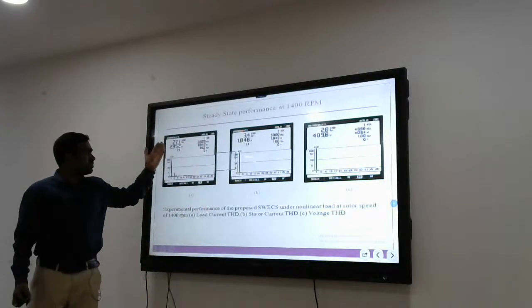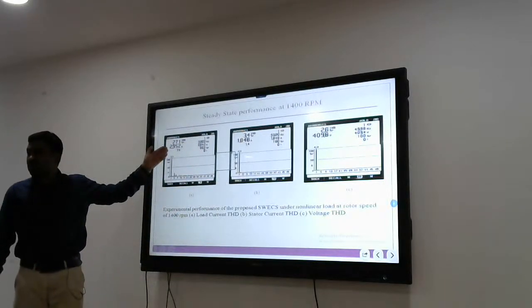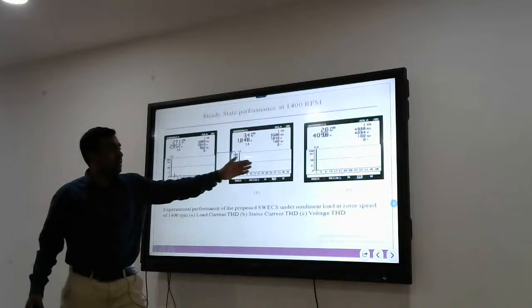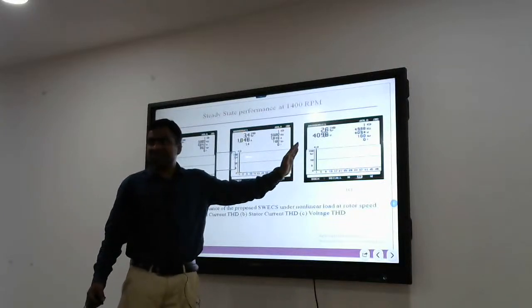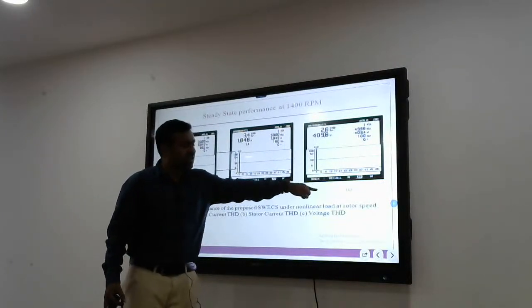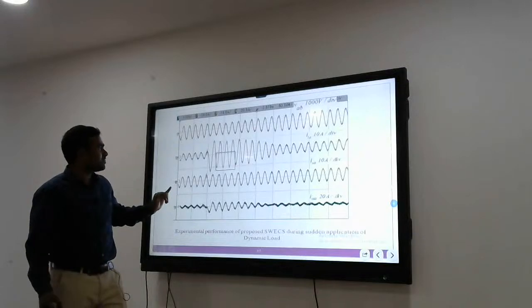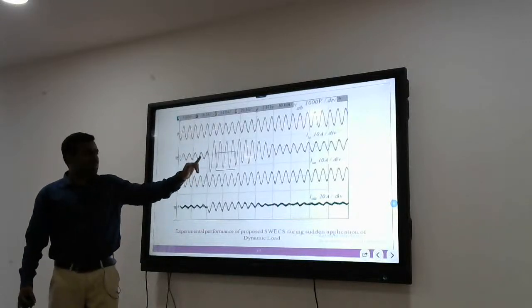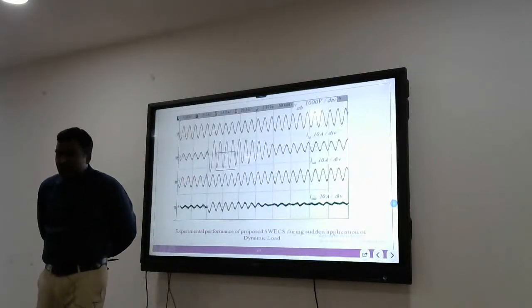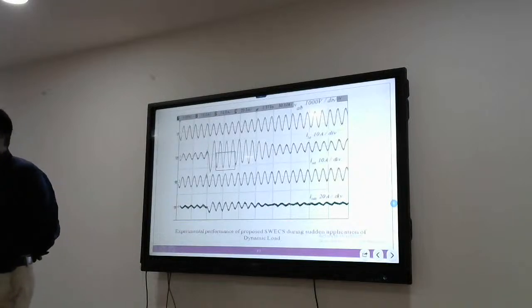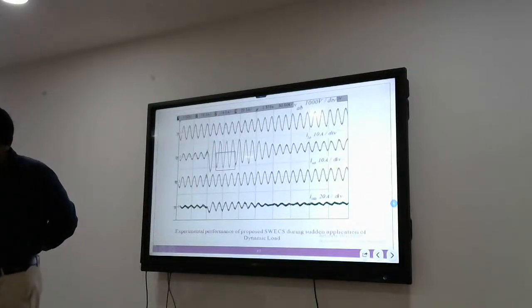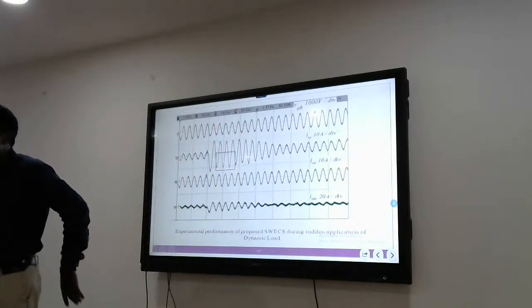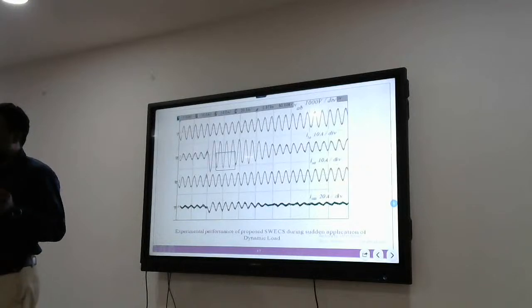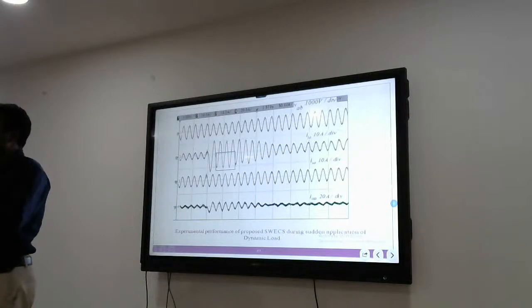See, the load THD is 27.1%, but our stator THD is still 2.6%. It's maintained well. One more thing: we have developed this, it's okay, good. These are hardware results. But if you suddenly put a single phase load, a motor load, normally in houses we have water pumps.